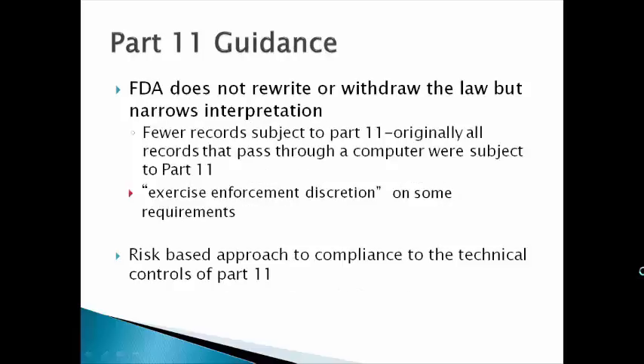The guidance narrowed the interpretation of the law, stating that fewer records will be subject to Part 11. Originally under the law, all records that passed through a computer were subject to Part 11. Now they are narrowing that interpretation. They also said in the guidance that they will exercise enforcement discretion on some requirements, meaning they will not enforce some of the more restrictive requirements that are in the law.